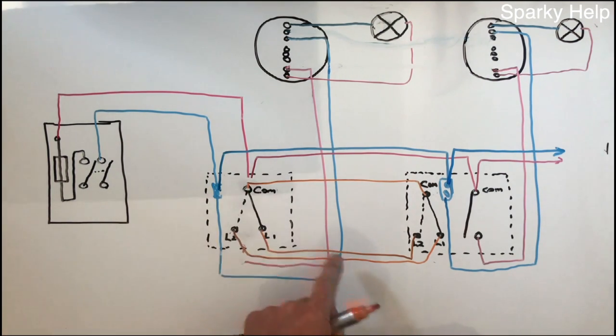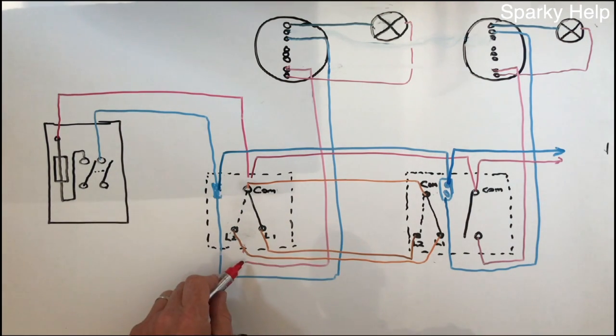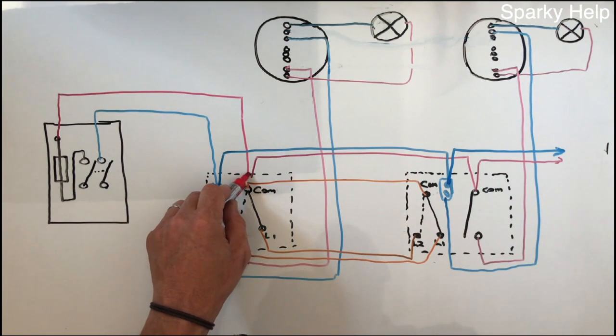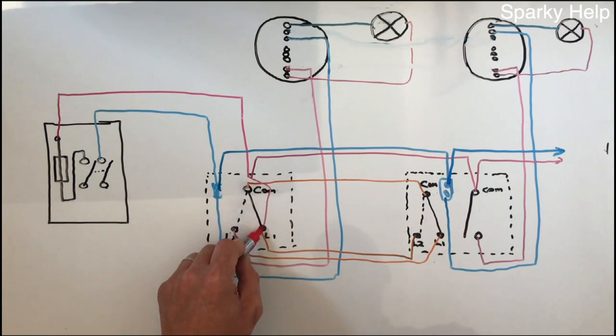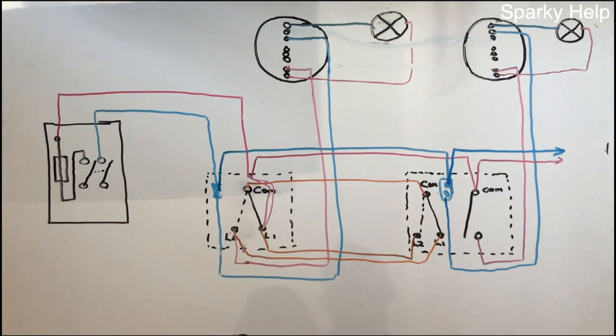We've now got to connect these back in, and remember, they don't go in the common anymore. You need to take one into L1 and one into L2, so these two are going to connect into there. And now we have a two-way.